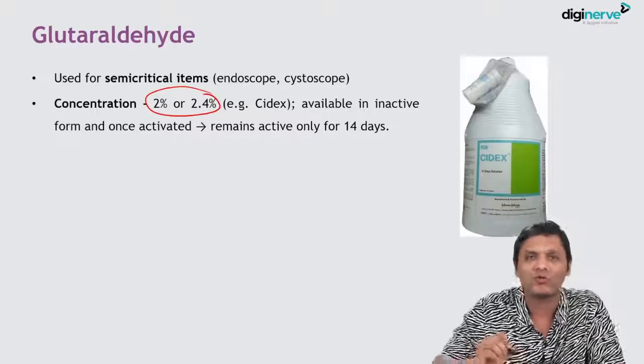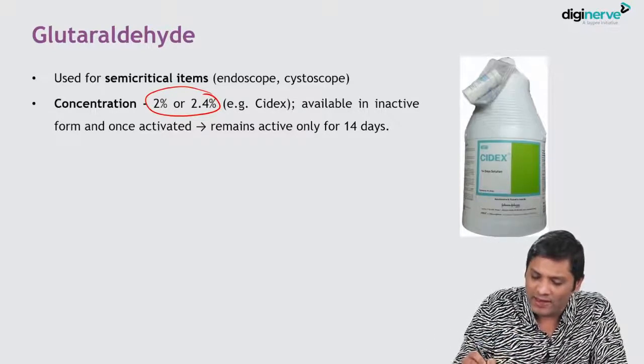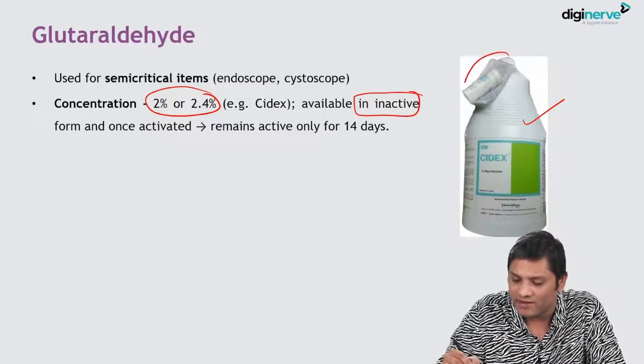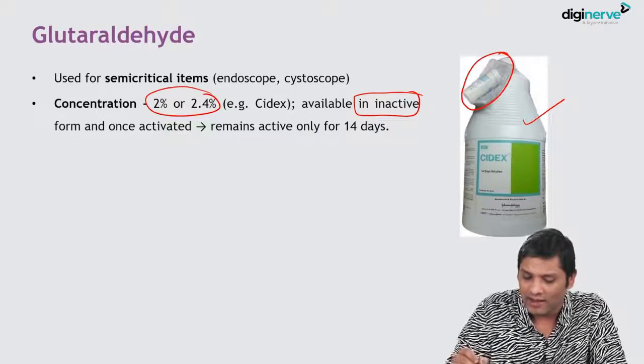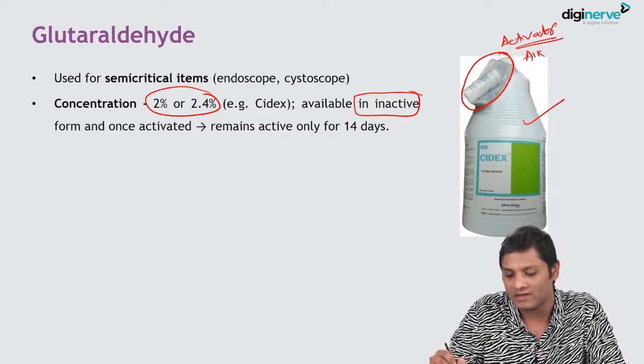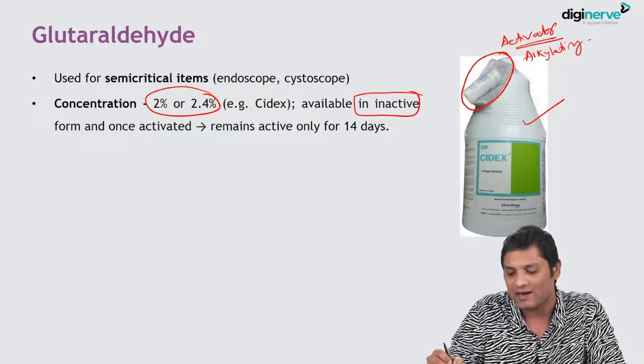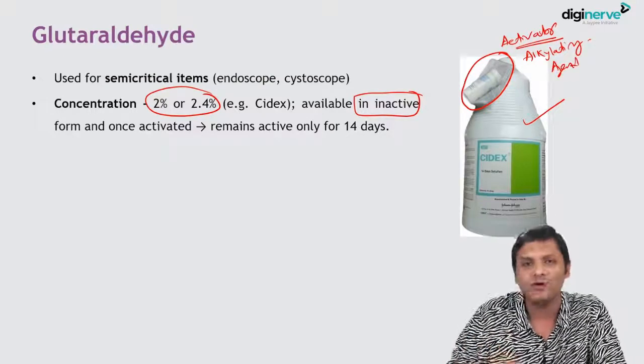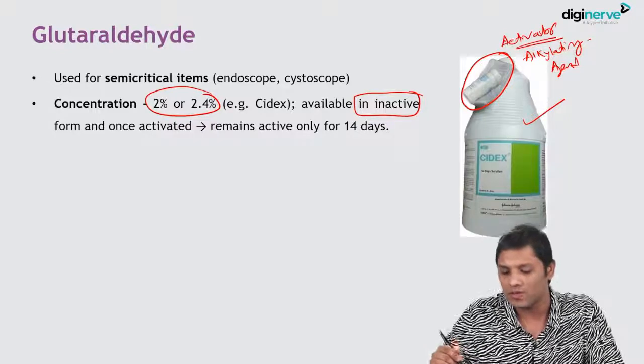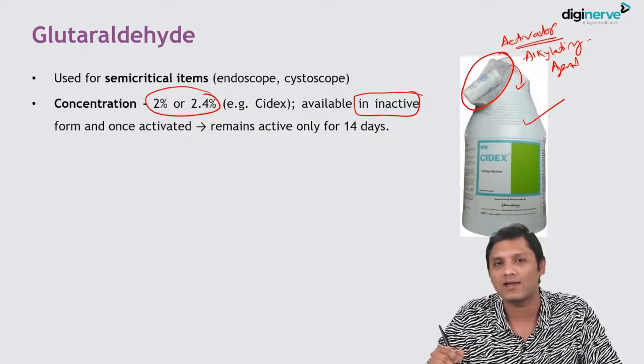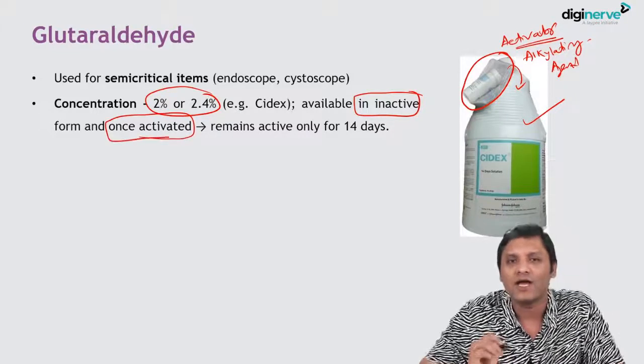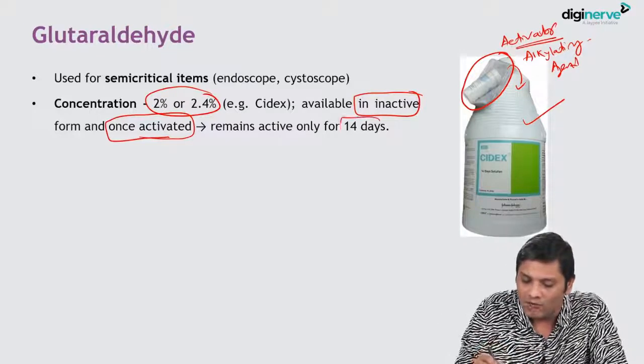Glutaraldehyde is usually available in a concentration of 2 to 2.4 percent, in inactive form. It is always available along with an activator, which is an alkalizing agent. When you open the glutaraldehyde box, you must add and mix the activator with it so that it becomes activated. Once activated, it will work efficiently for only 14 days.